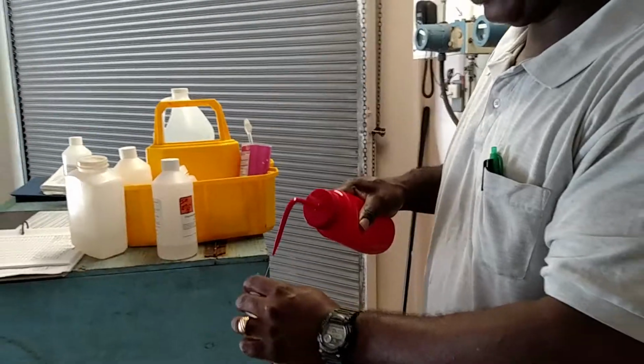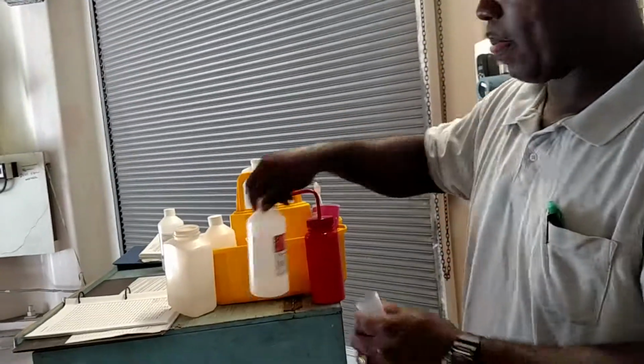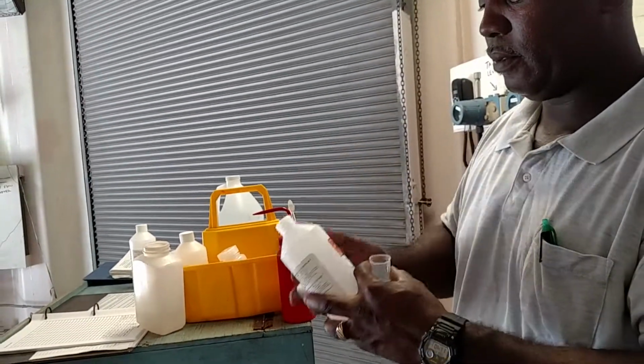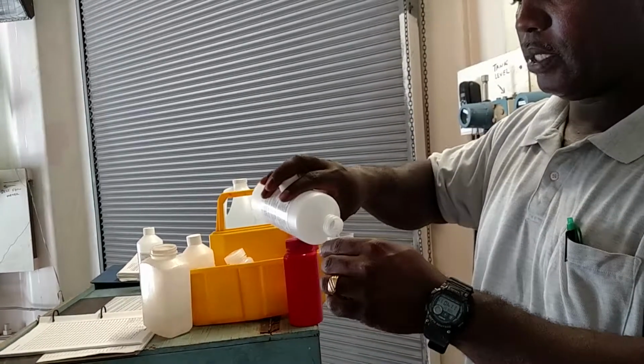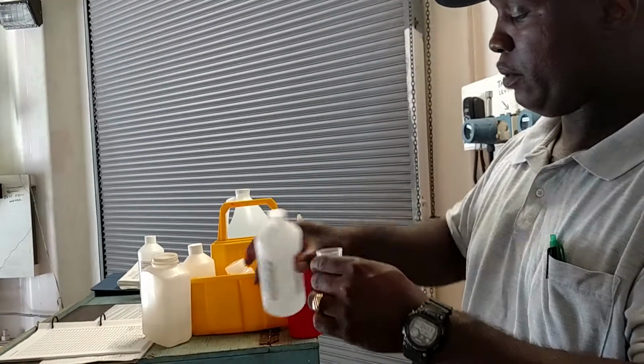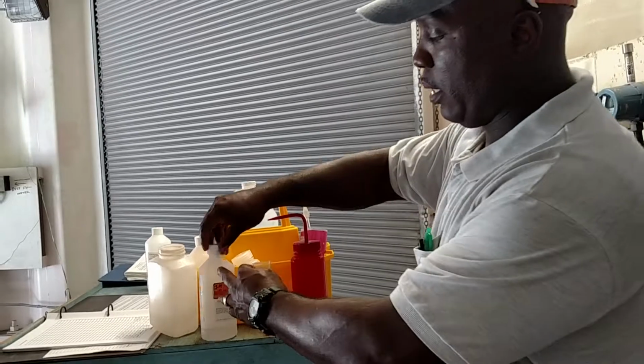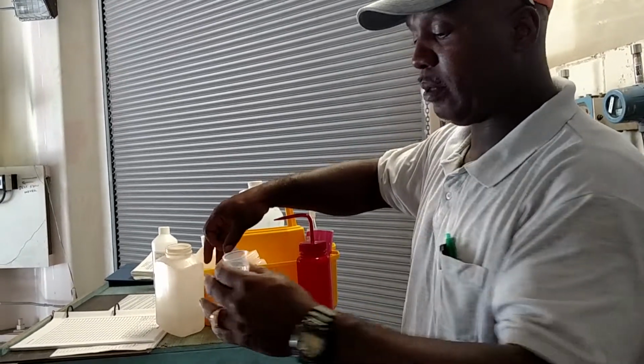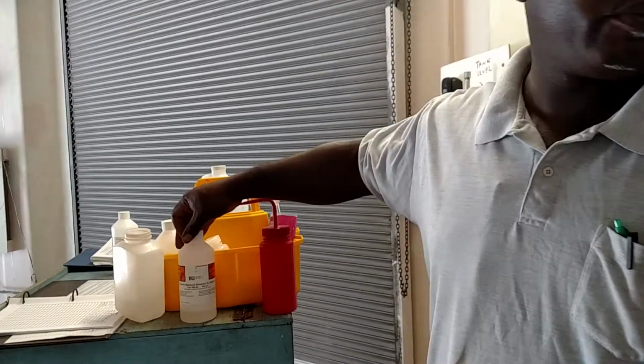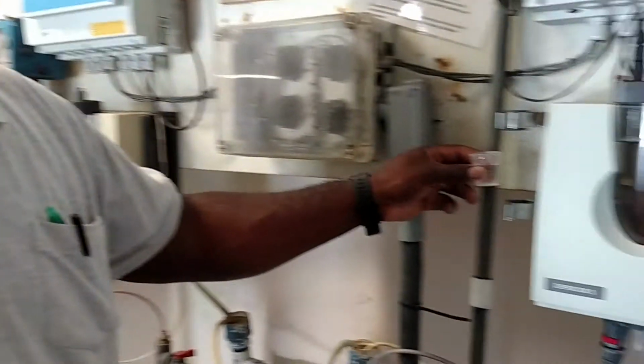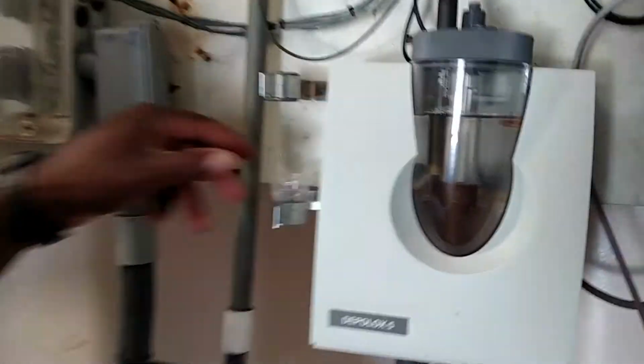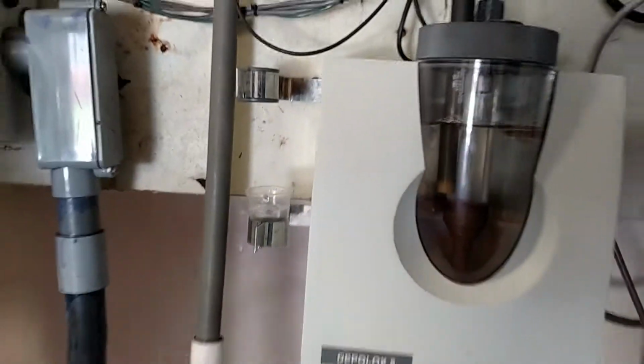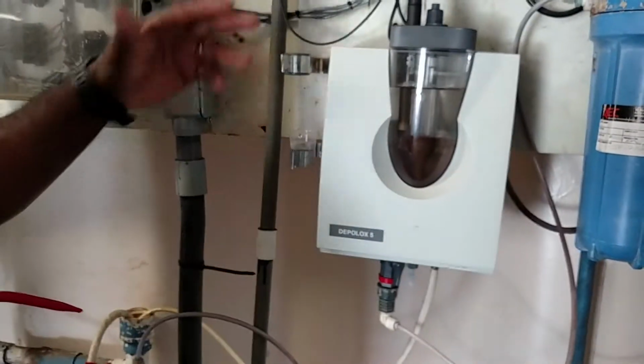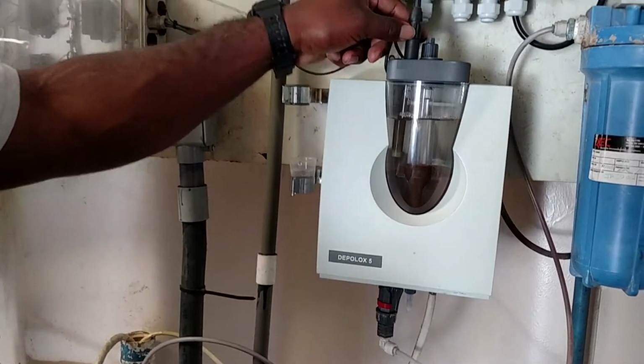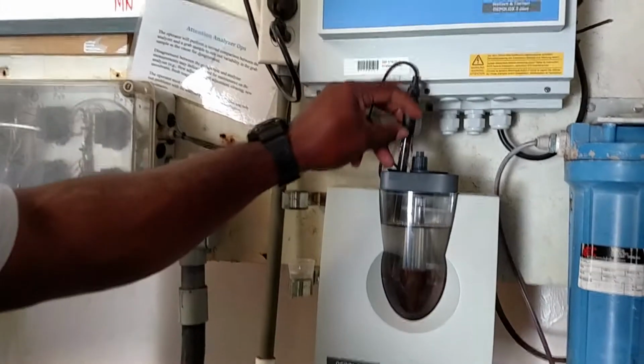Then I pour up, or rinse out. And I pour up my 0.2 standard, which is for my 0. And there's no specific amount. I probably put about 3/4 in there to kind of keep the probe submerged. And they got the little holders over here so I can put them in. Some of them you're going to see that you have to set it up on top because the probe doesn't get in once you set it in like that. So I slide my probe out.